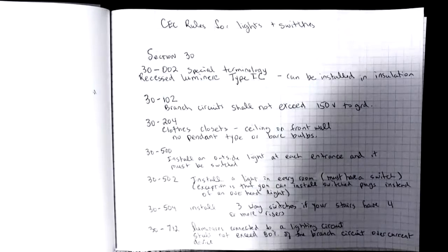30-002 under special terminology speaks to a recessed light fixture. If you're going to install that into an attic space that has insulation, you're going to need to make sure that those are type IC. If they're just installed between floors, say in the ceiling space above your main floor and your second floor where there isn't going to be insulation, then it's not necessary to get type IC.